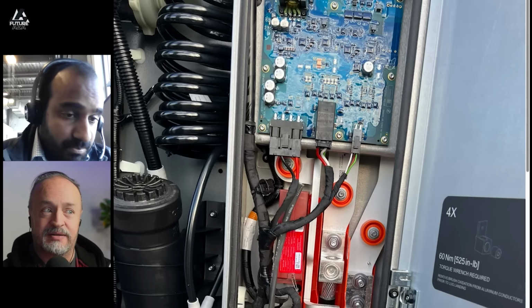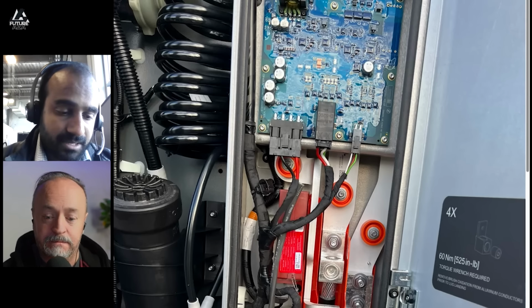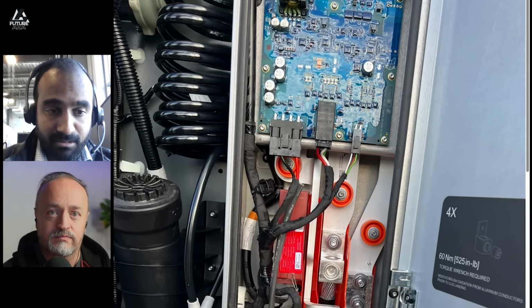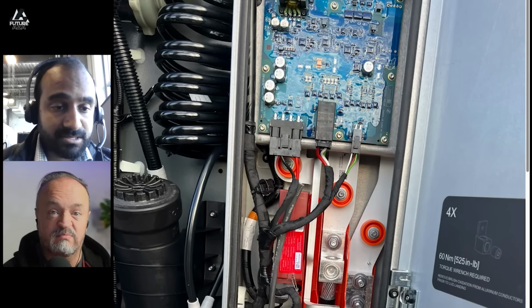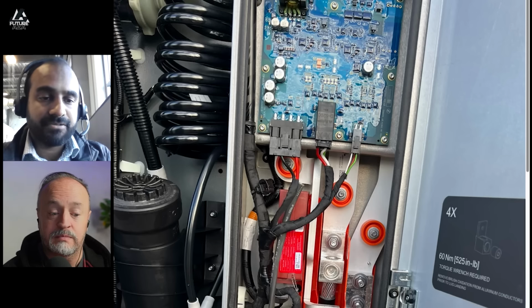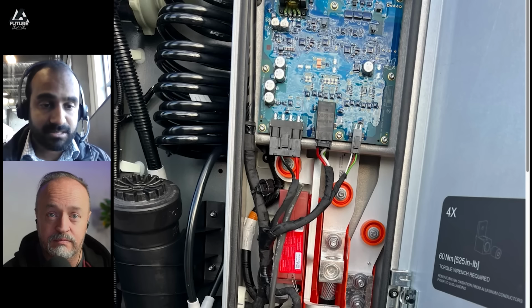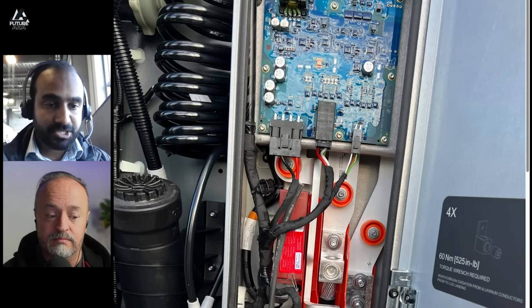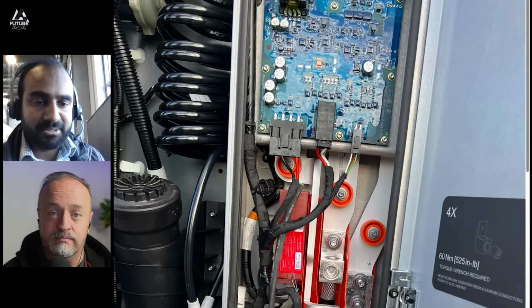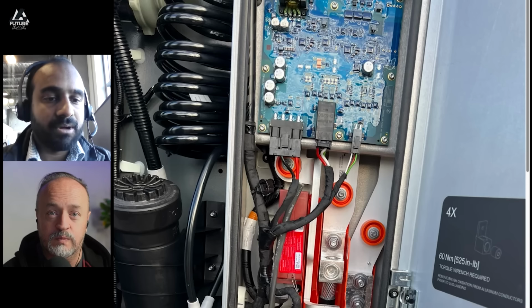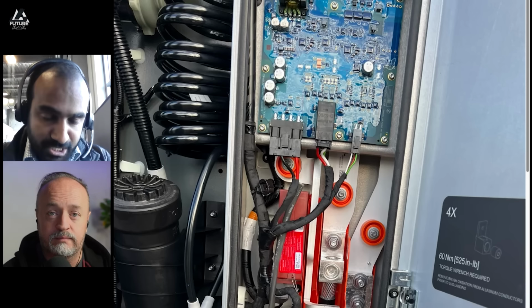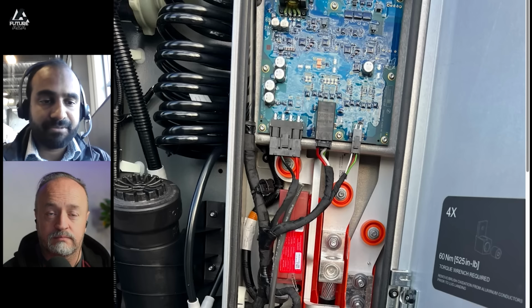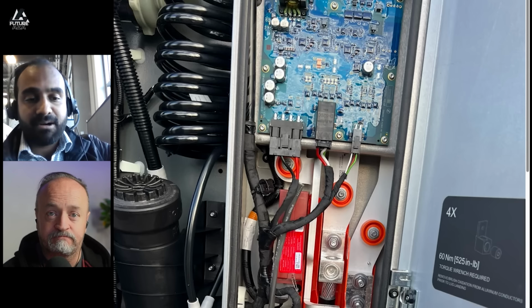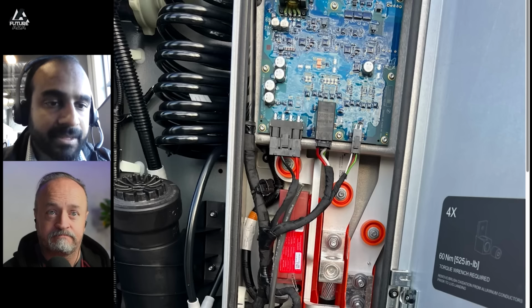And so that's pretty good, but you could imagine at 100 kilowatts, that's 5 kilowatts of heat, and we actually measure heat generated in terms of kilowatts - it's equivalent to just power. So when we design cooling systems, we actually think about what is the total amount of heat rejection that they need to perform, and we say we want to target 5 kilowatts of heat rejection or something like that.